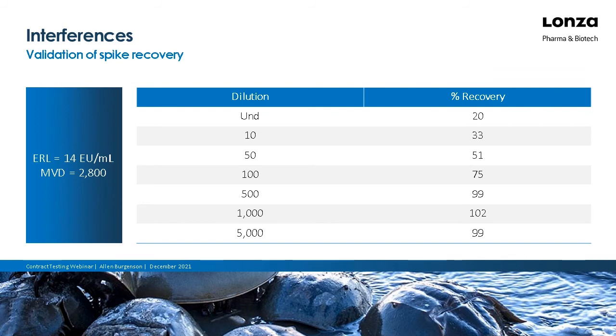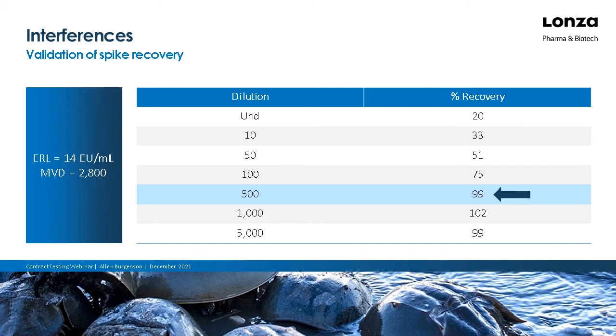So if you were doing your spike recovery and you see this result, the first result that you come to that is acceptable, quote unquote acceptable, is 1 to 50. However, we wouldn't recommend that because it's right at the edge. 75 is good, but 500 is probably better because your maximum valid dilution is 2800, and this gives you closer to 100%. And as you can see, this is what we would recommend.